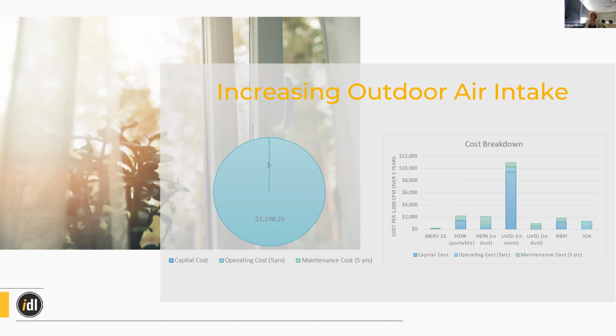We didn't include maintenance cost here, with the assumption that increasing your outdoor air intake, if it's a non-DOAS, a non-dedicated outdoor air system, isn't really feasible. It's going to be too hard for your HVAC to maintain temperature and humidity control. If it's taking in all of this really, really cold air, and then it's having to take all the humidity out and then rehumidify it. It's just a lot of wear and tear on your HVAC if it's not designed that way.